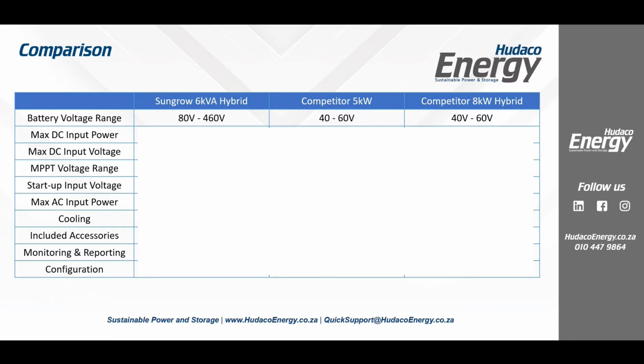Battery voltage range. Even the ones they call high voltage are actually only 52 volt, so let's call it 60 volt in terms of the battery range. In our particular case, we go 80 volts to 460 volts. There are 2 very big benefits to this. The first one is your balance of plant cost. We've already discussed the fact that you've got a 6mm cable red, 6mm cable black, and a 6mm earth cable. What's that cost? About 60 Rand. So that's your balance of plant cost there. Everything else is provided for you, and we can do that because we're running these high voltages. We also don't need any other protection in between. It's already included in the cost. So that's the first thing.